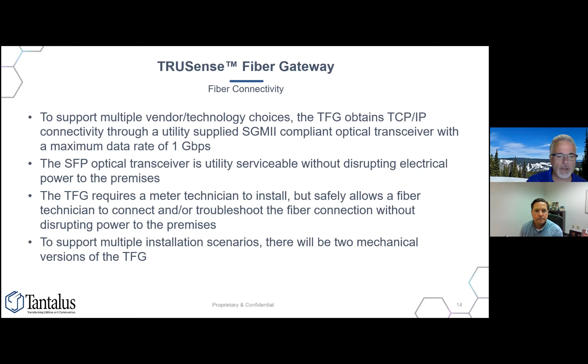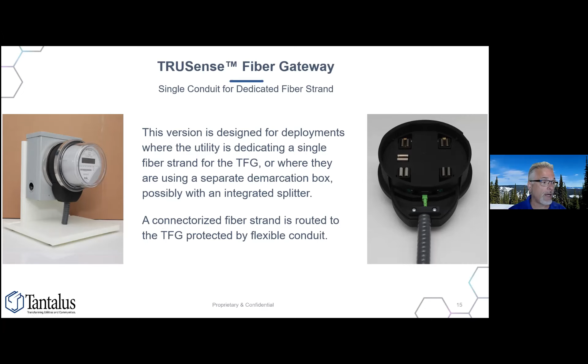This is the one we just had at the Fiber Connect show, our first prototype. This device has a single conduit going into the bottom, for a dedicated fiber strand. This version is designed for deployments where you have a dedicated single fiber strand used for smart grid, or where perhaps you're using a separate demarcation box you already have out there, which may or may not have an integrated splitter. You might be running multiple fibers to the external demarcation box, and now you're going to light one up directly for this device. Basically, this device has you bring a connectorized fiber strand through this flexible conduit into the TFG, connecting it directly to the SFP optical transceiver that sits inside. And now you have internet connectivity and everything else.